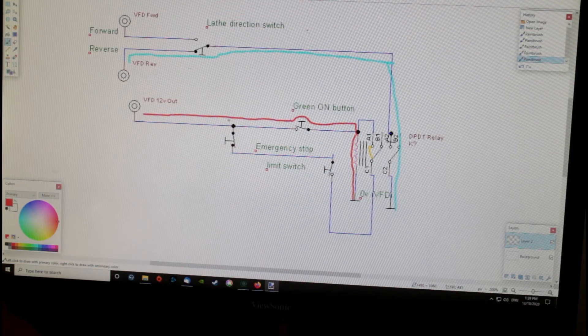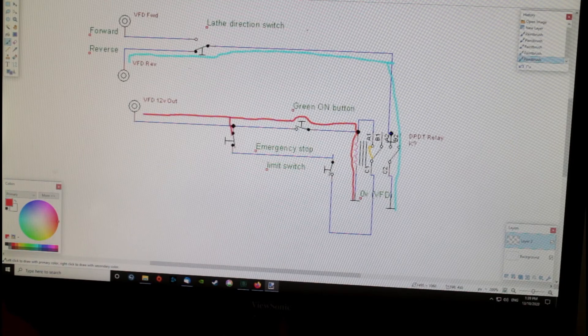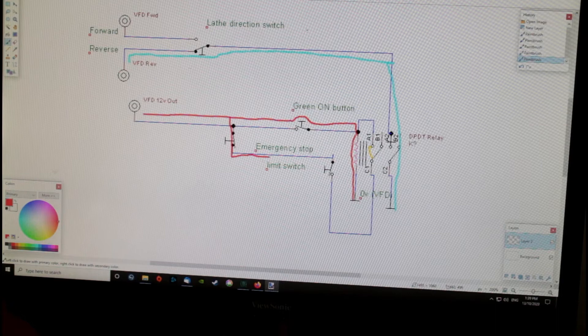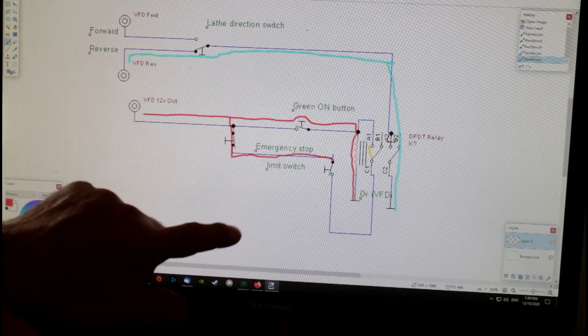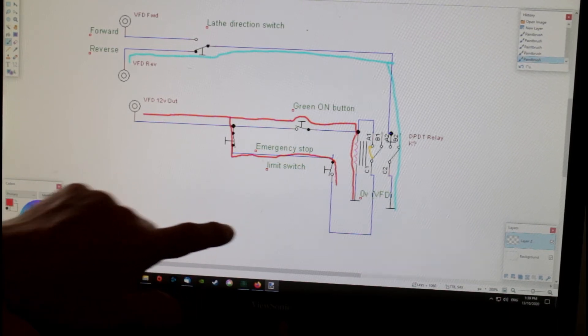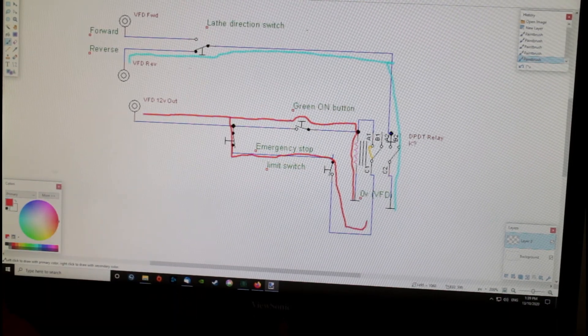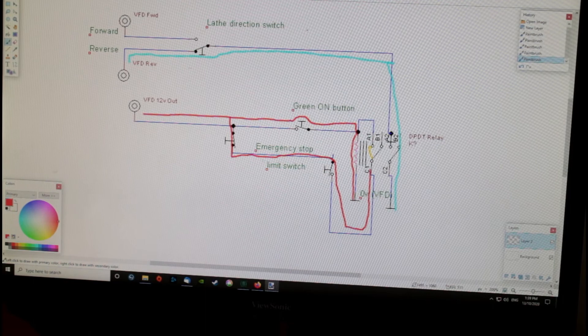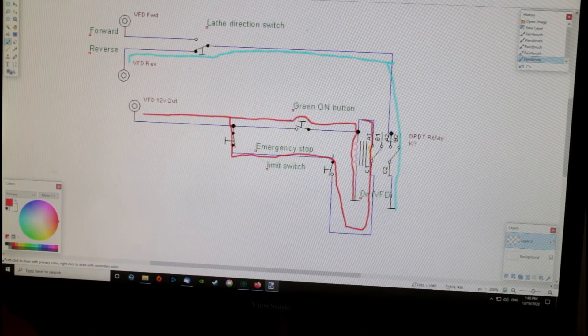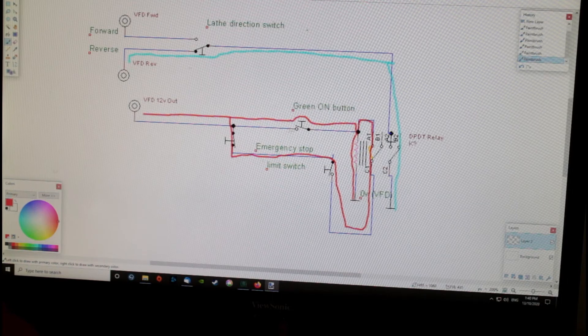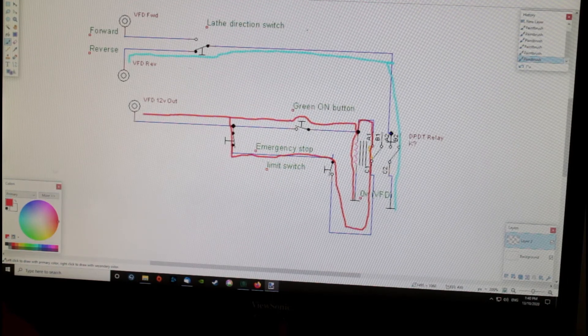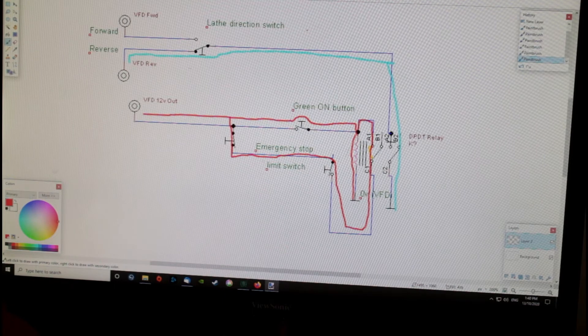The current also from here goes through the emergency stop button, which is in a closed position, through that limit switch, which is also closed when the guard is down, back up through this now-closed relay, and back to the coil. So it effectively creates a loop and keeps the relay on.